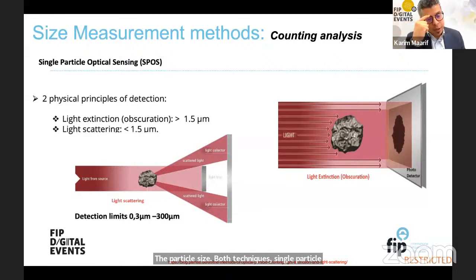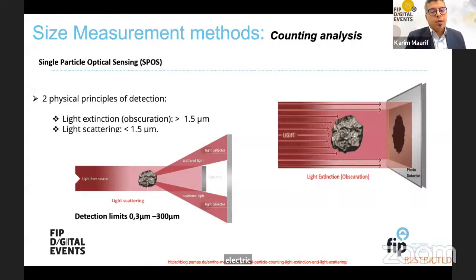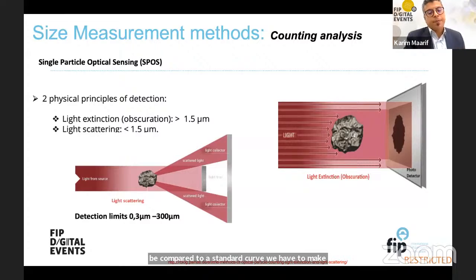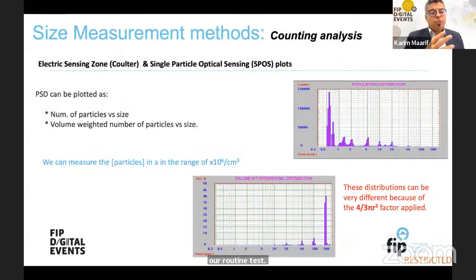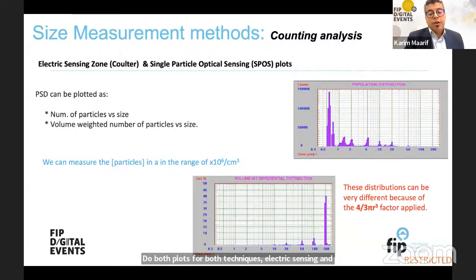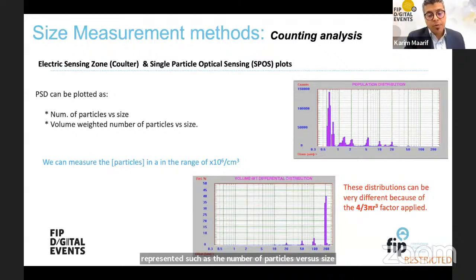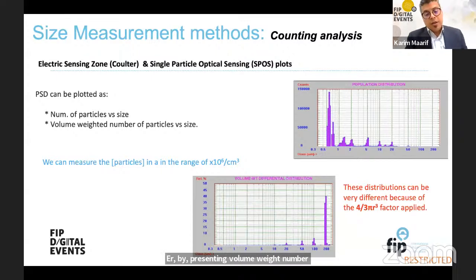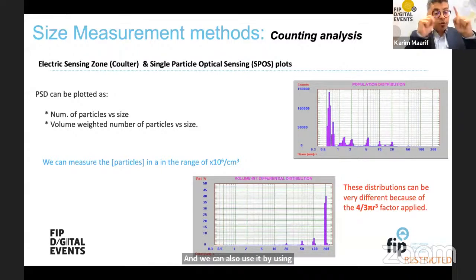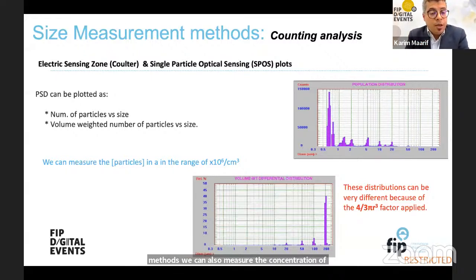Both single particle optical sensing and electrical particle sensing results can be compared to a standard curve made before routine testing. The plots for both techniques can be represented either as number of particles versus size, or by presenting volume, weight, and number versus particle size. Using these methods, we can also measure the concentration of particles in a range of one million per cubic centimeter.